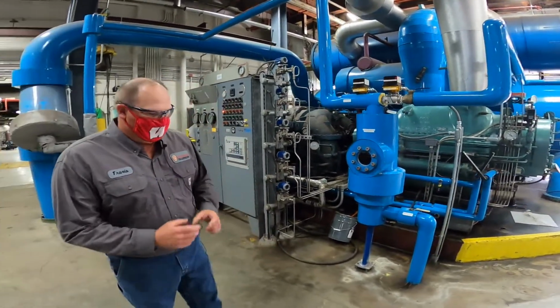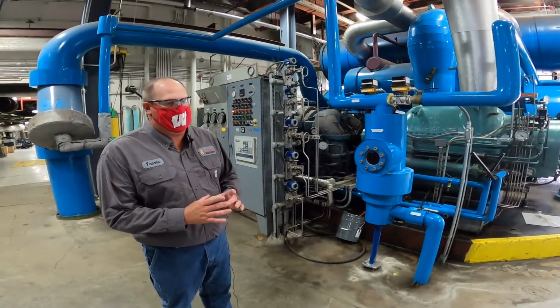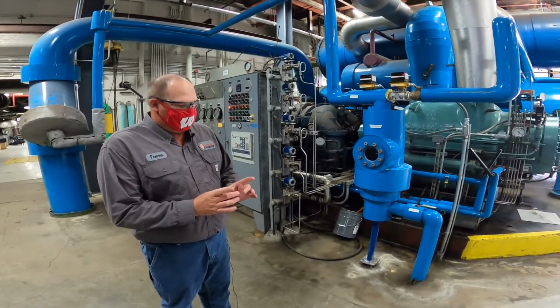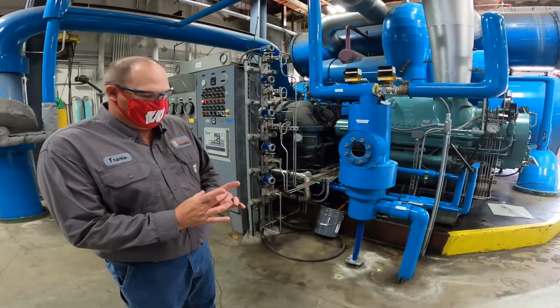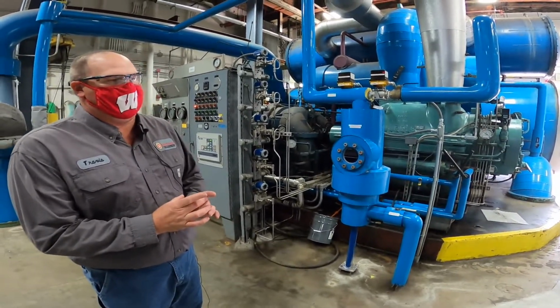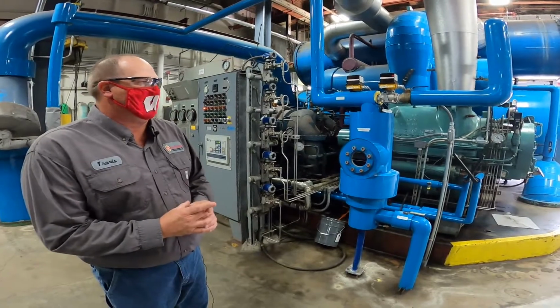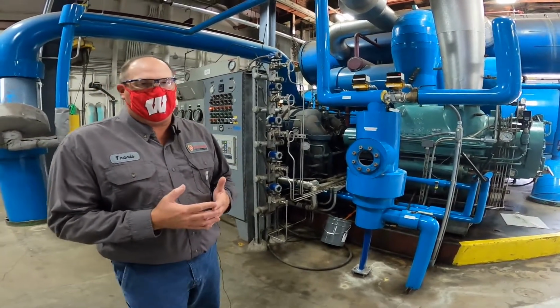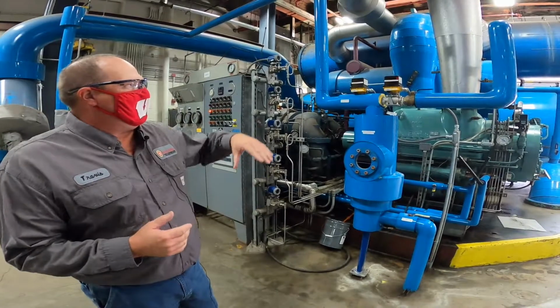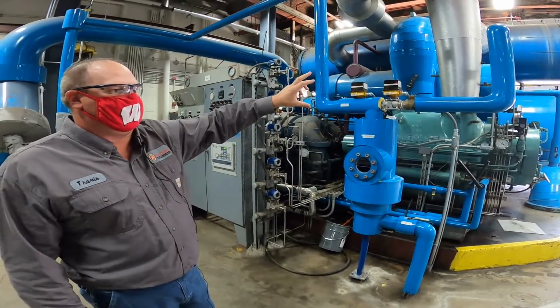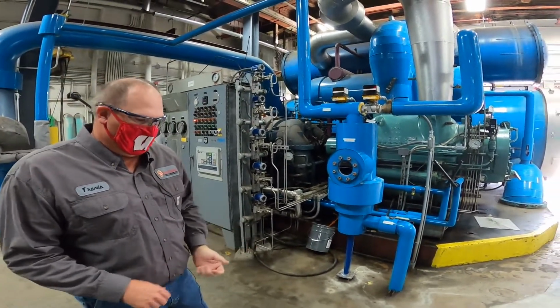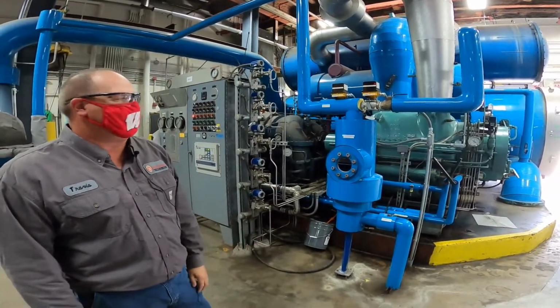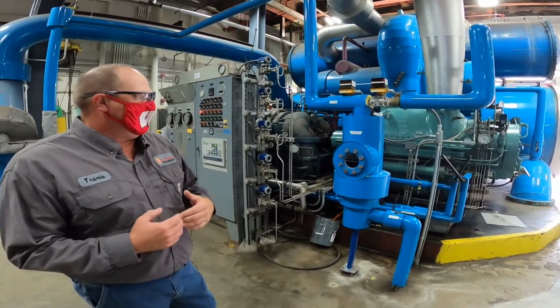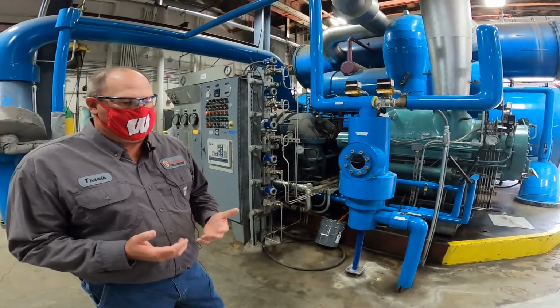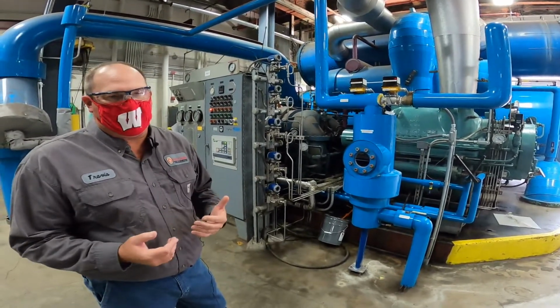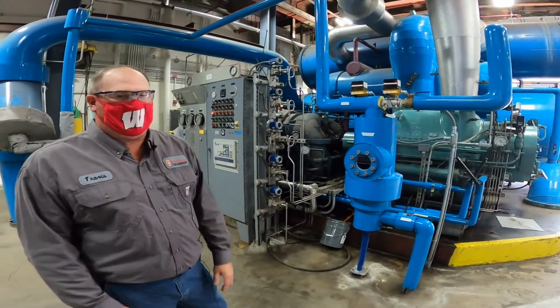We were able to use not just the energy data and savings, but we were also able to visually show with some millipore samples how much cleaner the water was in the unit at the end of the year when we took the chiller offline. Plus it saves us labor-wise and safety, because we have to take these lids off every winter and manually punch those tubes, one tube at a time with a long cable and a brush. If we can get at least 2 or 3 years where we don't have to do that, we save over 2,000 hours of manual labor.